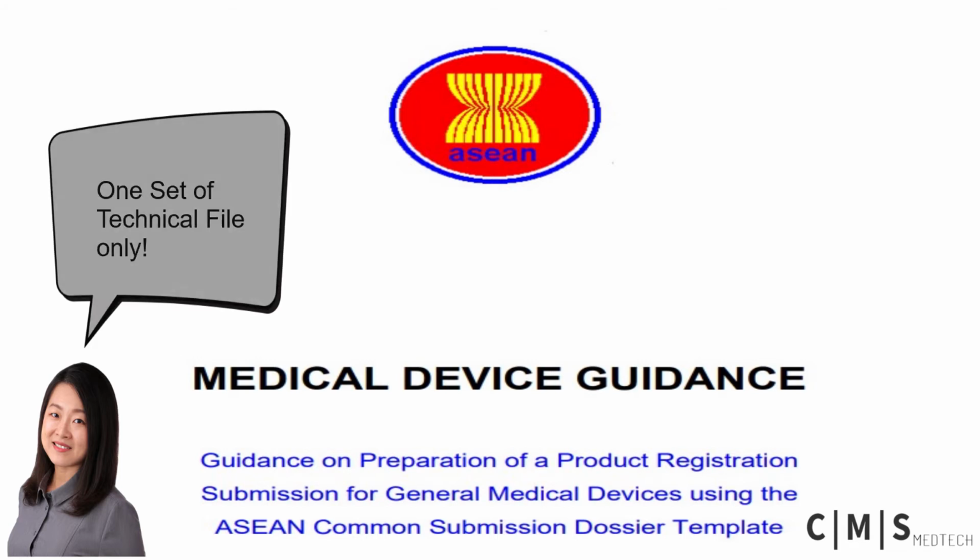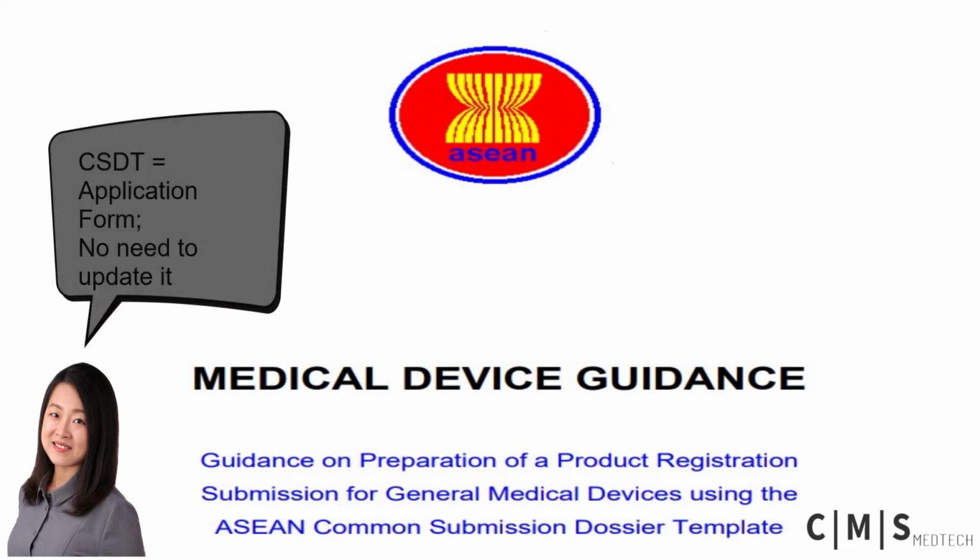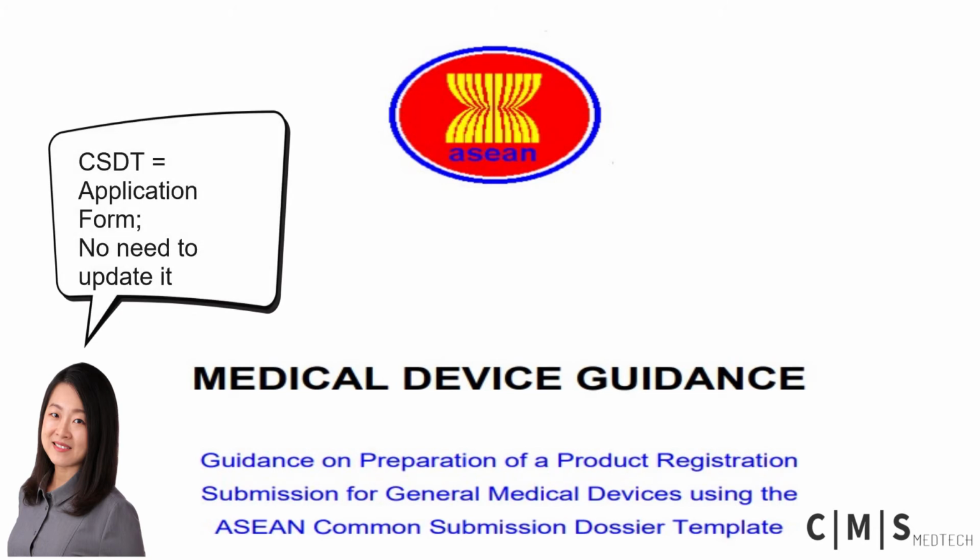The manufacturer also needs to maintain one set of technical file for one group of medical device only. The CSDT, however, is actually more like an application form. Once the CSDT is submitted and approved, there is no need to maintain it anymore. Further changes to the medical device, if any, would be notified to the ASEAN authorities through other means, as stipulated by each ASEAN authority respectively.